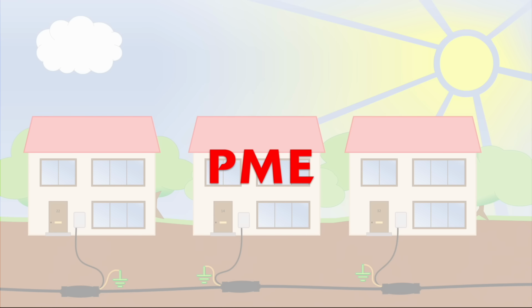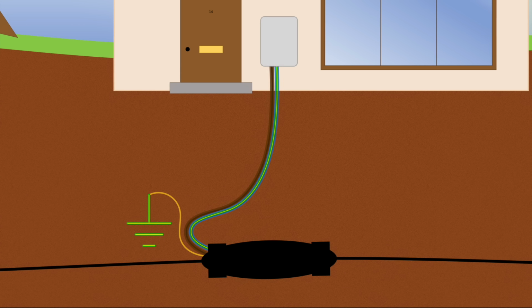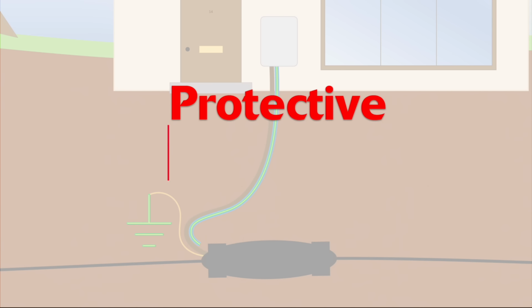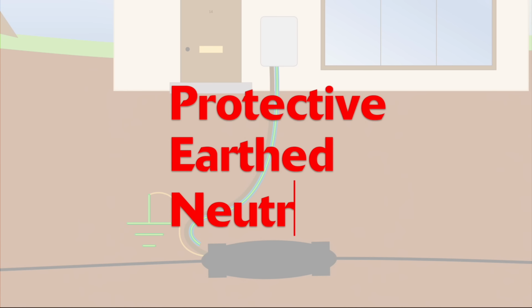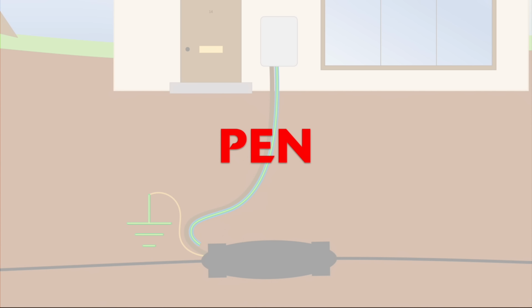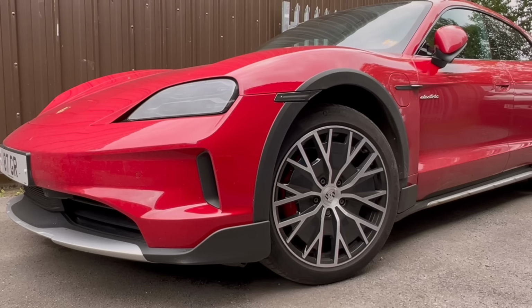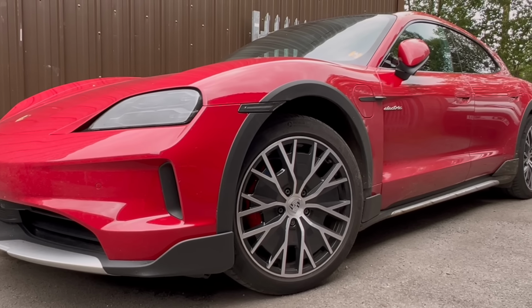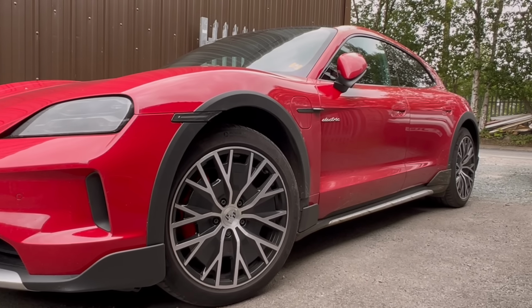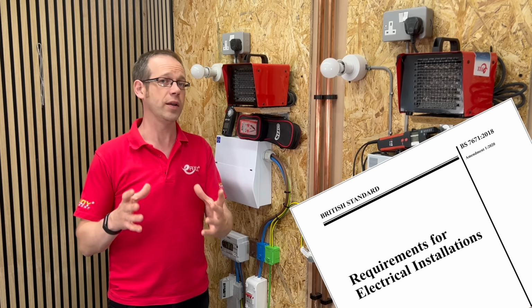Unfortunately, some of these connections to the main supply cable are starting to fail. When this happens, the earth and neutral connection to the property can be lost, and because we've lost the protective earth and neutral connection, we refer to this as a PEN fault. The prospect of this was especially worrying when EVs started to become popular, because you'd end up with a big lump of metal on the driveway at 230 volts. This led directly to Amendment 1 of the 18th edition.